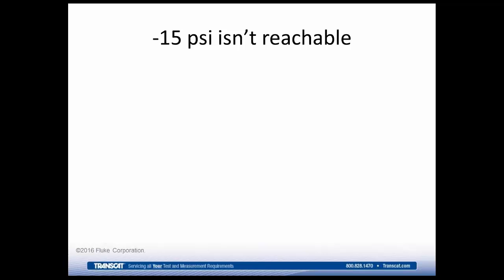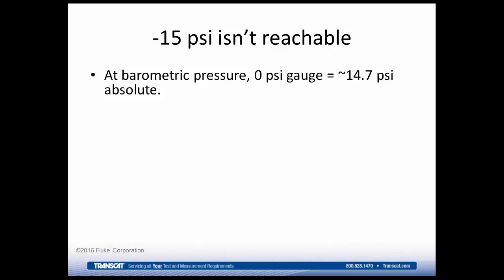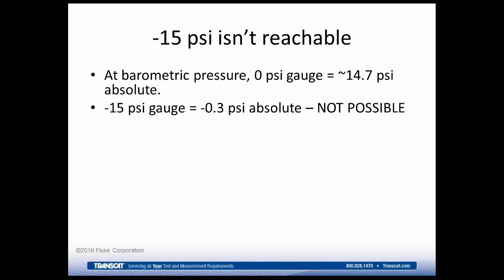A common question we get is, okay, your data sheet says negative 15, but I can't actually get to negative 15. The thing's broke. What's wrong with it? Well, let's step back and look at it a bit. At barometric pressure, we've defined that barometric pressure is 0 psi gauge. It's also approximately 14.7 psi absolute. So we're now saying that I want 15 psi below barometric pressure. That's negative 15 psi gauge, which is negative 0.3 psi absolute.